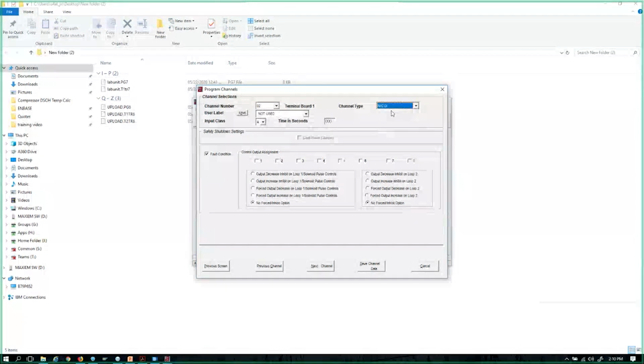And so sometimes that becomes critical as far as maybe a supervisor in a packaging facility might print a report, and then that tech can go out on the shop floor and he or she knows, hey, I'm supposed to wire these channels up normally closed. I'm supposed to wire these channels up normally open. This day and time, it's probably not so much the case, but that's one option that it can be used for. But it absolutely changes nothing in the software when you select normally open or normally closed. They're going to work both the same way mechanically.